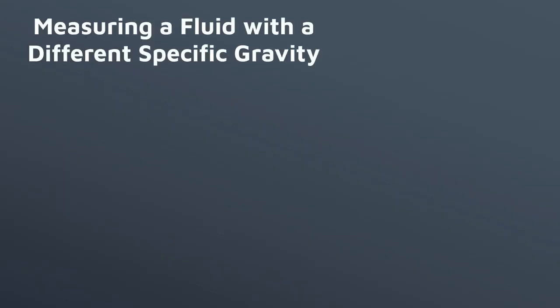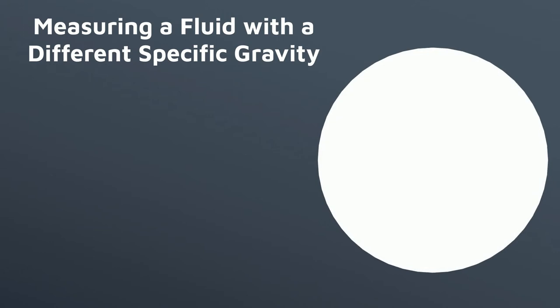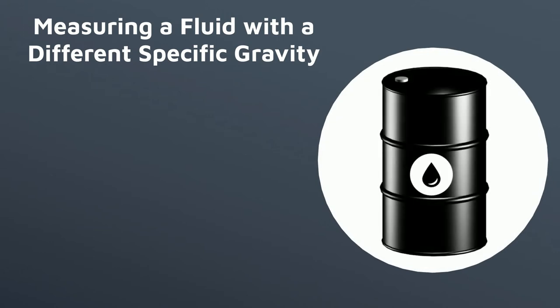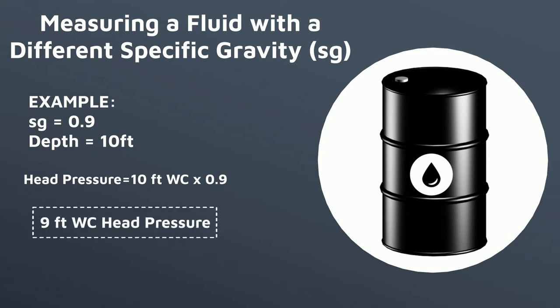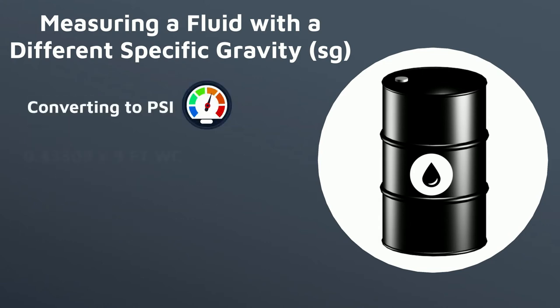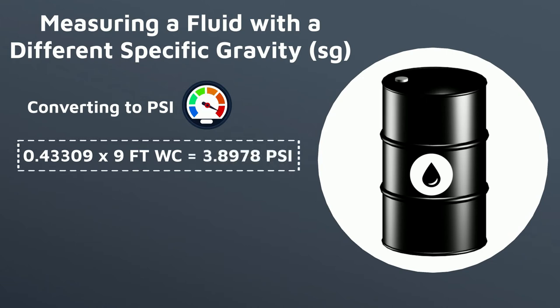If you are measuring a fluid that has a different specific gravity, such as oil, you need to find the specific gravity and calculate your total head pressure. Using our example above, if the specific gravity was 0.9 and the depth is 10 feet, head pressure would equal 10 feet times 0.9, giving a water column head pressure of 9 feet. Converting to psi would equal 0.433 times 9 feet of water column, equaling 3.89 psi.